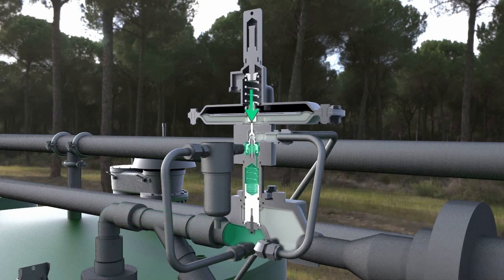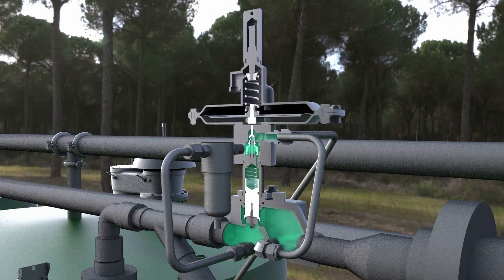the set pressure spring will push down on the spindle and evacuate the pressure above the piston. As the pressure above the piston evacuates, the valve will open and introduce the blanketing gas inside of the tank's vapor space.